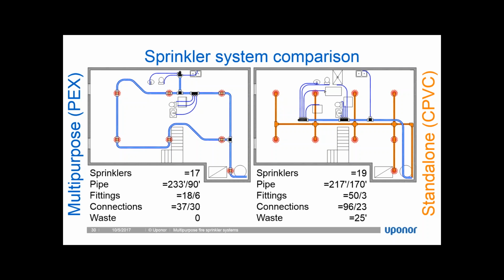And also, if this was an 8-plex where I had 4 units on the front of the building and 4 units on the back of the building in a back-to-back configuration, well, I would only have open space on 2 sides on the corner units. The 2 middle units on each side, I would only have 1 side open, and then it wouldn't meet the requirements of NFPA 13D. At that point, we would switch to NFPA 13R, and you would be looking at a different type of material at that point.